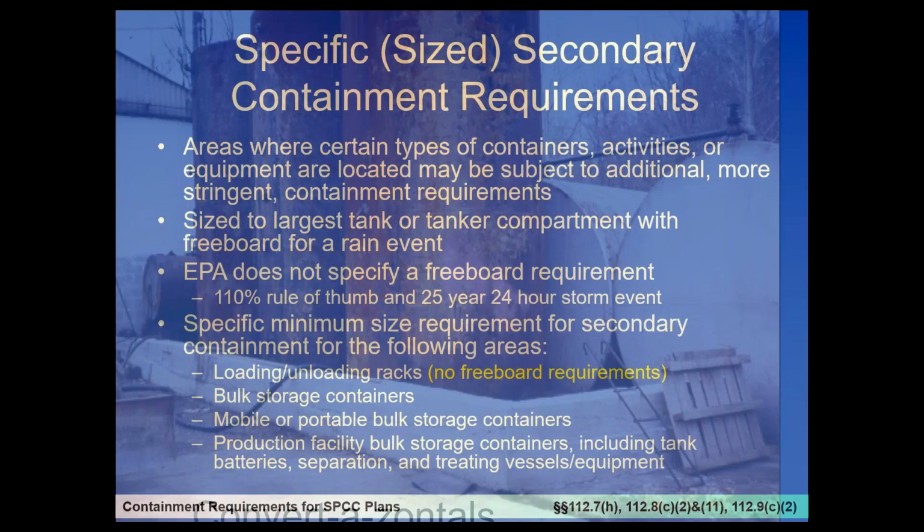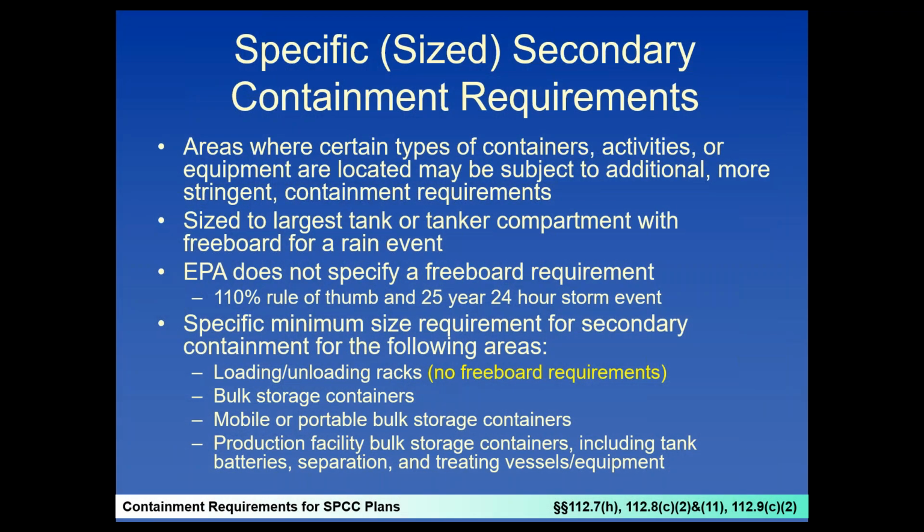And what this facility has done here is put underground storage tanks above ground. That is not allowed under our program. We call those convertizontals. Okay, so what do you have to have? You have to have sized containment.